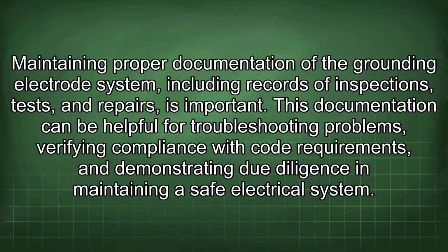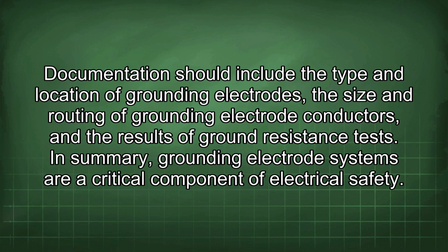Maintaining proper documentation of the grounding electrode system, including records of inspections, tests, and repairs, is important. This documentation can be helpful for troubleshooting problems, verifying compliance with code requirements, and demonstrating due diligence in maintaining a safe electrical system. Documentation should include the type and location of grounding electrodes, the size and routing of grounding electrode conductors, and the results of ground resistance tests.